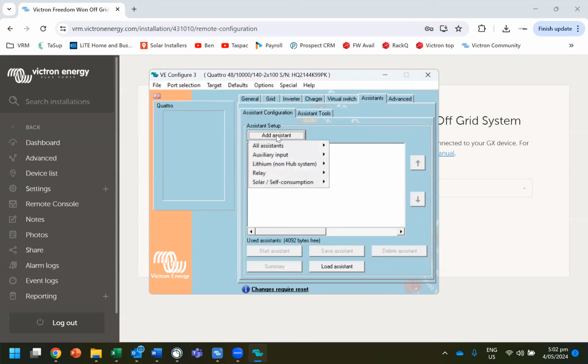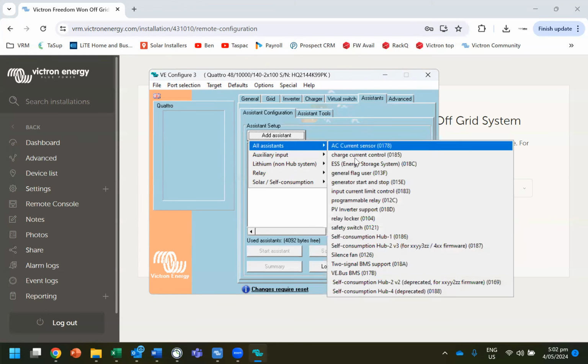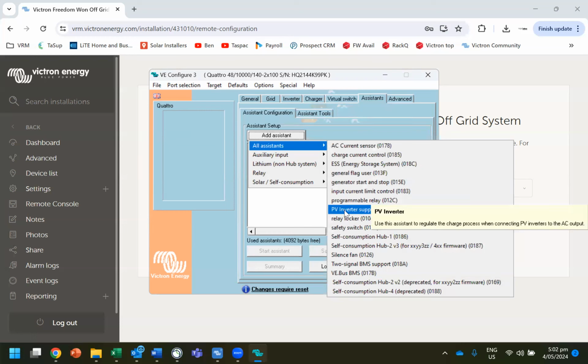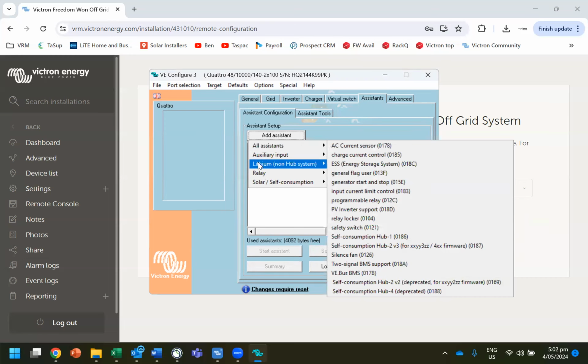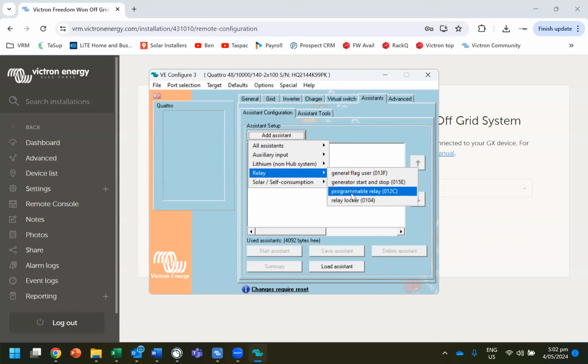Assistance. So if you have an AC coupled PV array, then you'll put PV inverter support. And that will then frequency shift to ramp back PV. You may also do a relay assistant where you go programmable relay, and then you can turn the AC2 output on and off based on certain settings like state of charge. And that may be useful so that when the battery's full, you can turn a hot water element on so the solar actually continues to be used for something useful on the site, and the hot water cylinder starts getting heated up.